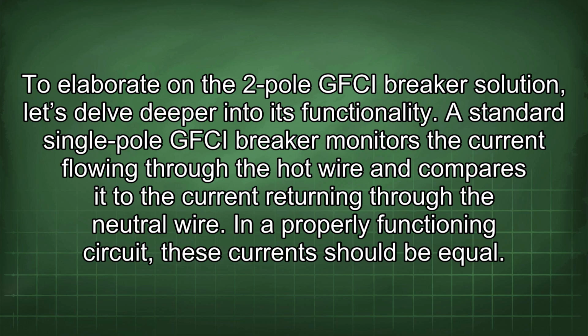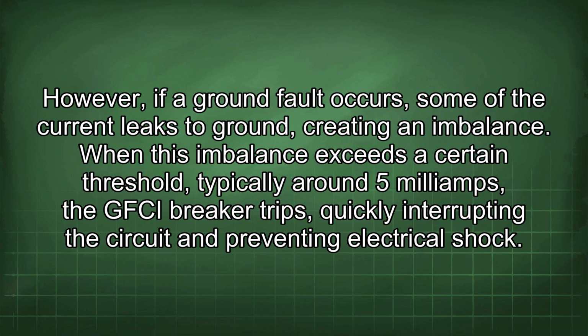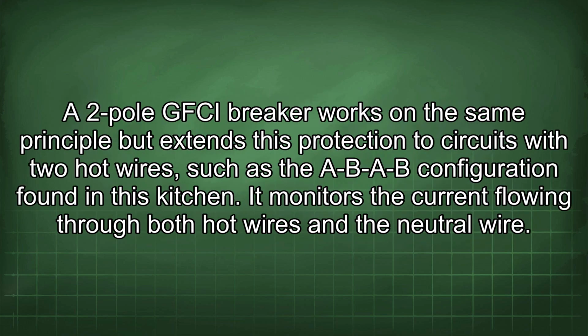A standard single-pole GFCI breaker monitors the current flowing through the hot wire and compares it to the current returning through the neutral wire. In a properly functioning circuit, these currents should be equal. However, if a ground fault occurs, some of the current leaks to ground, creating an imbalance. When this imbalance exceeds a certain threshold, typically around 5 mA, the GFCI breaker trips, quickly interrupting the circuit and preventing electrical shock. A two-pole GFCI breaker works on the same principle but extends this protection to circuits with two hot wires, such as the A-B-A-B configuration found in this kitchen.